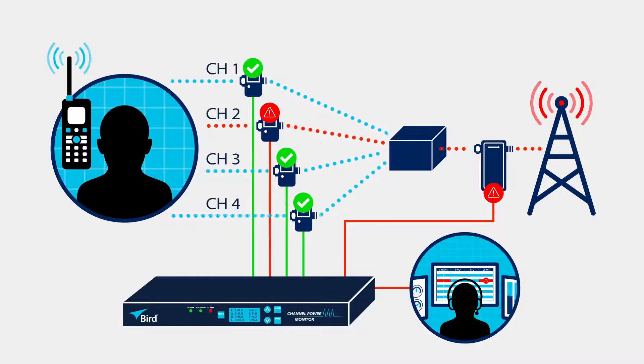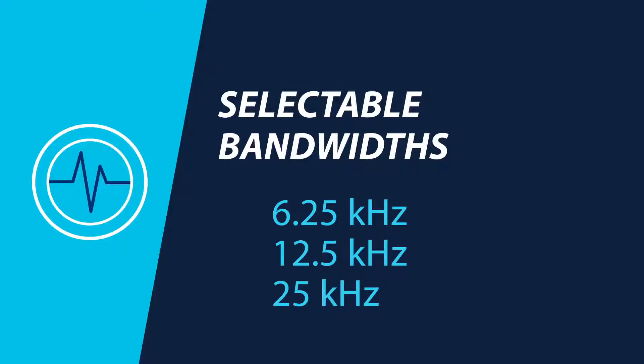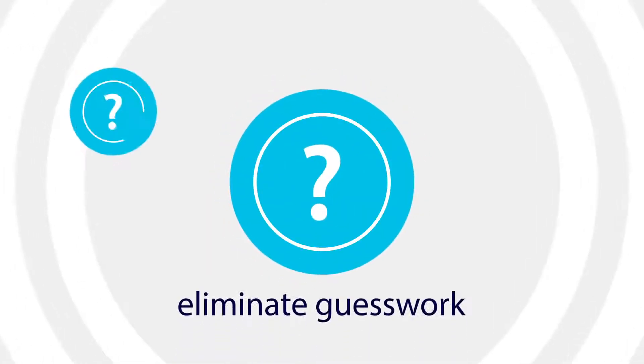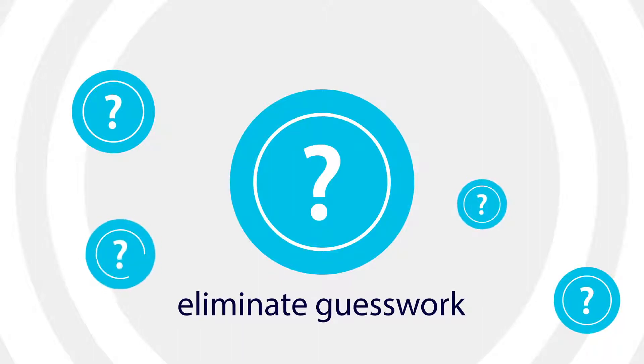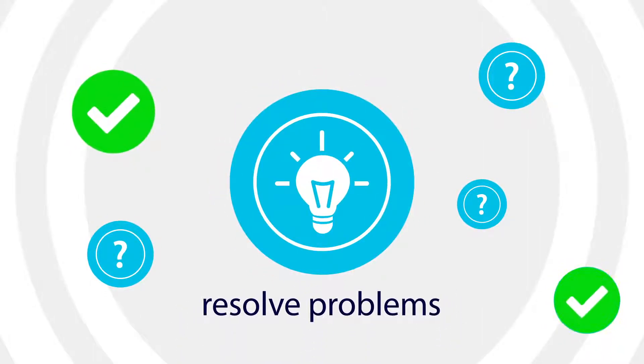With user-set alarm parameters, the CPM solution can sense, alert, identify, and locate radio communication issues, even down to selectable bandwidths of 6.25, 12.5, or 25 kilohertz. This eliminates guesswork and allows technicians to respond quickly and accurately, or even resolve problems before they become a downtime event.